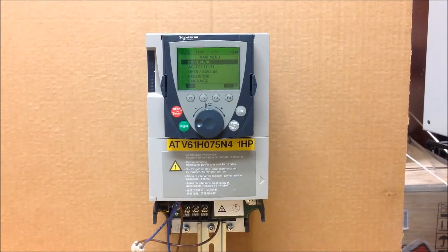Now the first thing that needs to be known here is that the drive's part numbers and the firmware versions of the drive you're trying to transfer from one to the next using this keypad will have to be the same. So you can't take an ATV61 rated for one horsepower and try to download parameters to another drive with different firmware.